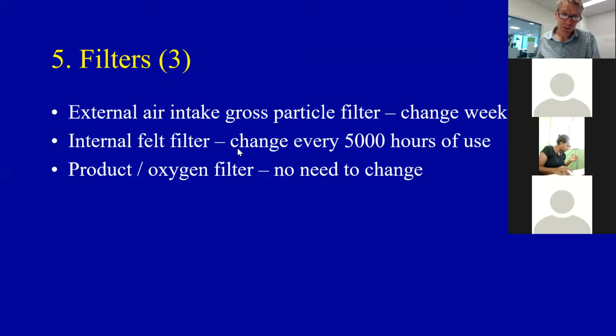The internal filter needs to be changed only every 5,000 hours of use, and the biomedical technologists know how to change this. This is easy to change, but it's inside. And then there's one more filter, which filters out even more microscopic particles, and that is called the product filter. After the product tank I showed you before, there's a product filter just before the oxygen gets delivered to a patient. There's no need to change that. That will last for the life of the concentrator.